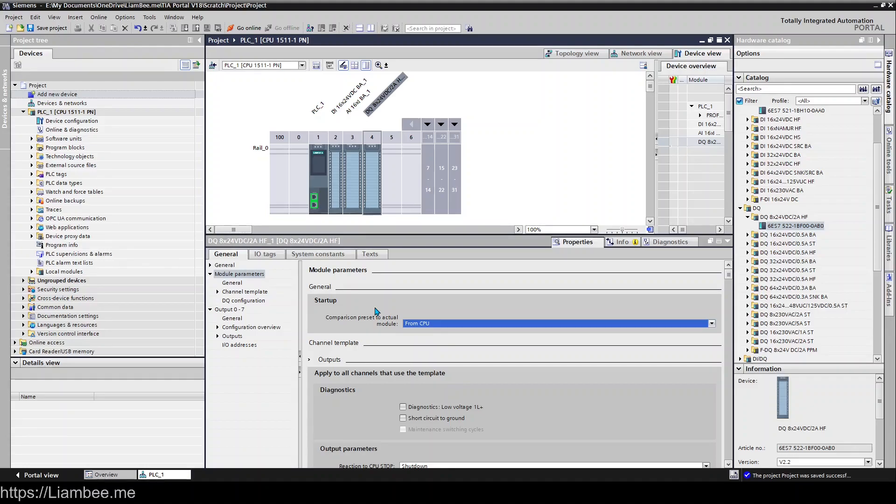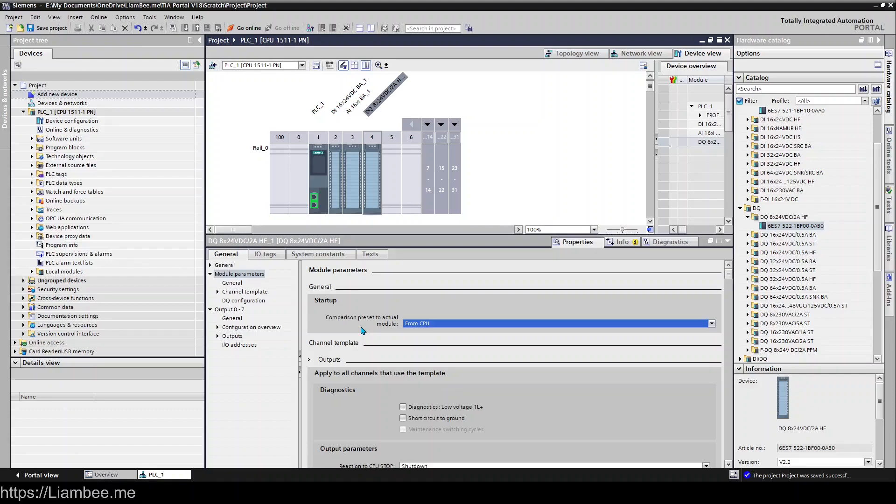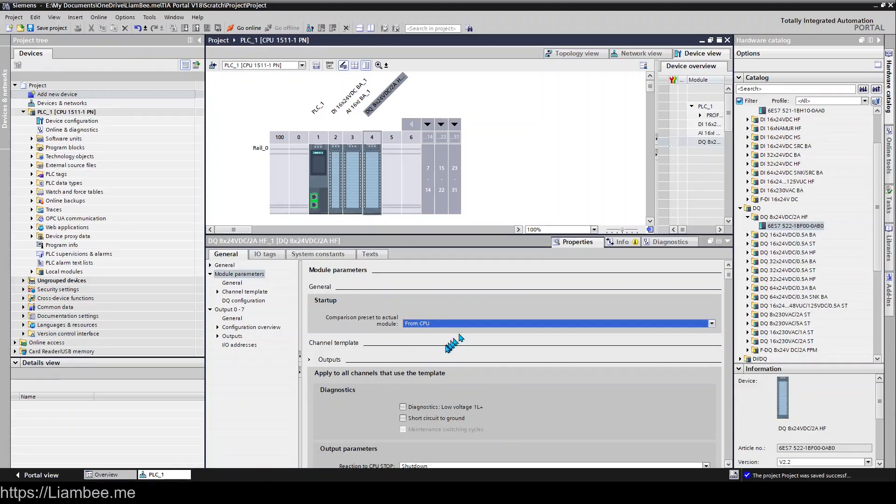This particular one here, startup comparison preset to actual module, all this is doing is making sure that we're happy that the correct type of output card has been installed compared to our TIA Portal program. All we're doing is saying start up CPU only if compatible, start up CPU even if there's a mismatch, or from the CPU. If you have a look at the help file on this, it gives you a little bit more information as to what these mean.